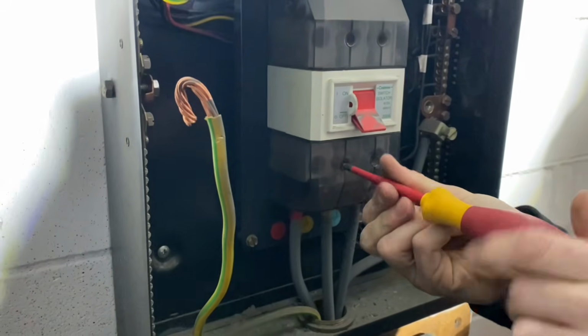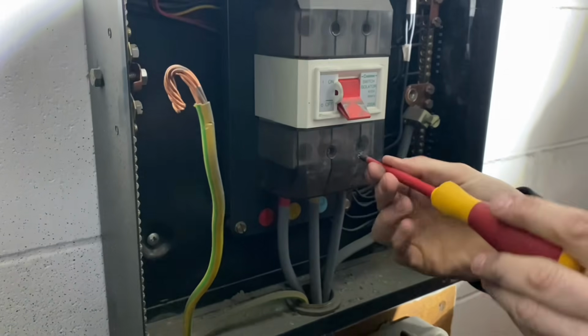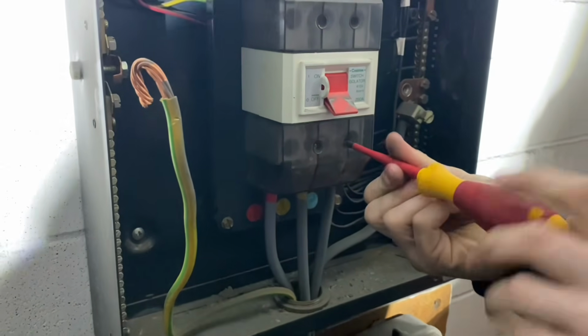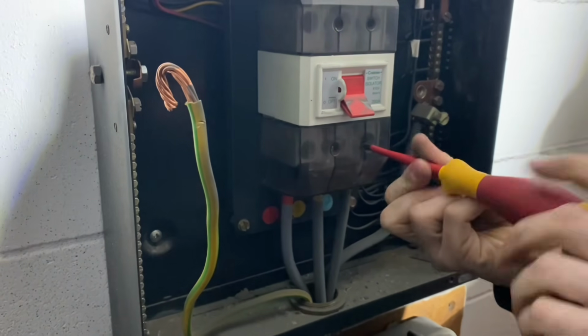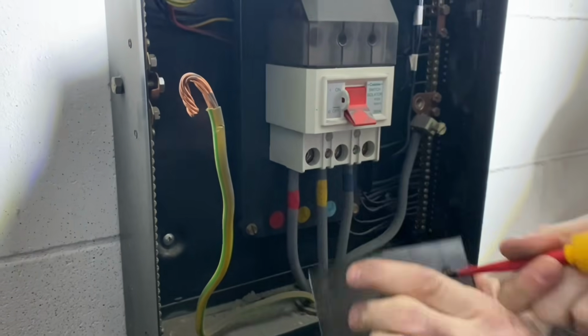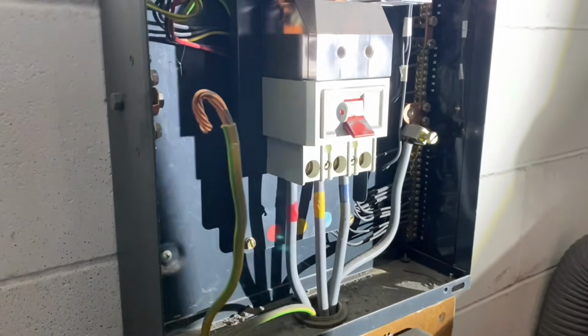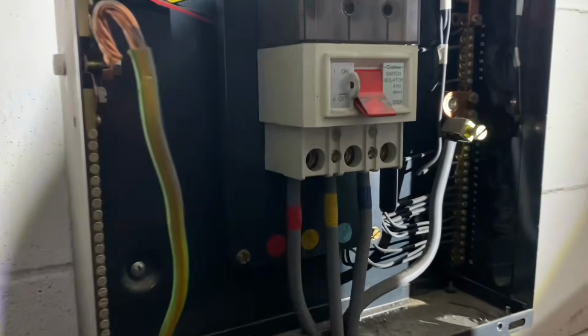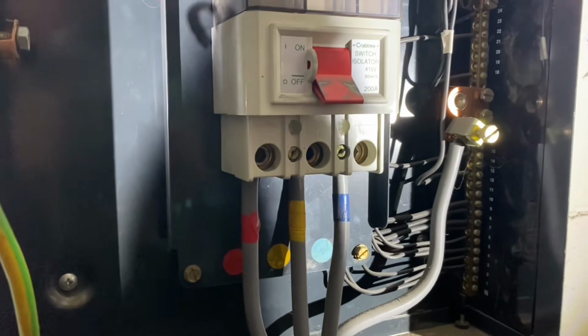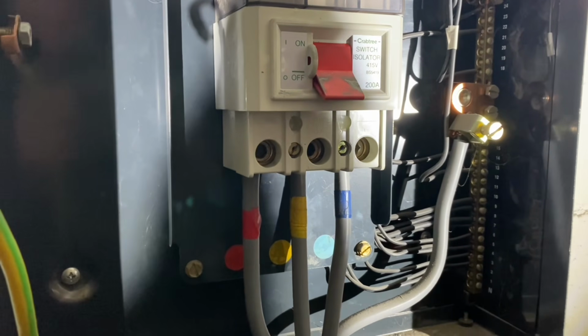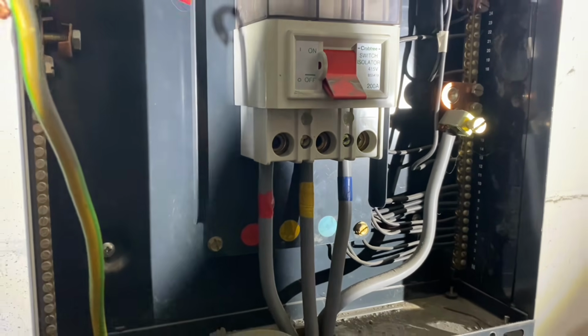Okay, so the earthing conductor's out. We're just going to drop this off. Right, we've got the earth out. Still take care, because obviously the bottom side of this is live. It is live. There is no remote isolator here. You might find in AM2 or AM2S there might be another isolator that you can turn this off with before removing it, but we're in the real world here. So they're now live at the bottom of that switch. They are, yeah. And it's red, yellow, blue, and not brown, black, grey.